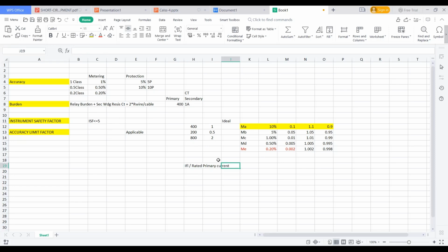If I take 5 as an example, the fault current is equal to 400 into 5. So up to 2000 amps flowing in the primary of the CT, the metering CT with this condition will not enter into saturation. Beyond 2000 amps, the CT might enter into saturation. That is the case for metering.